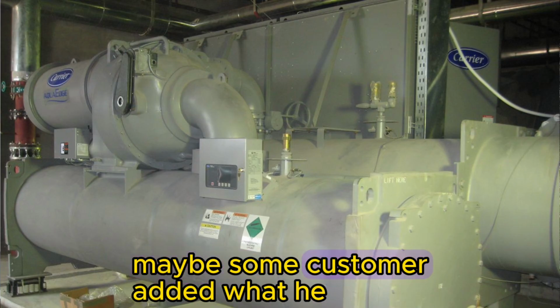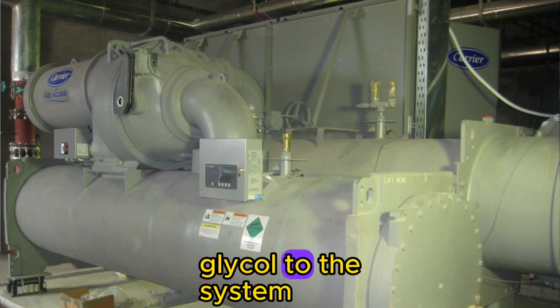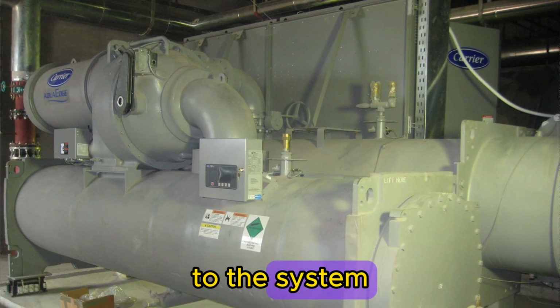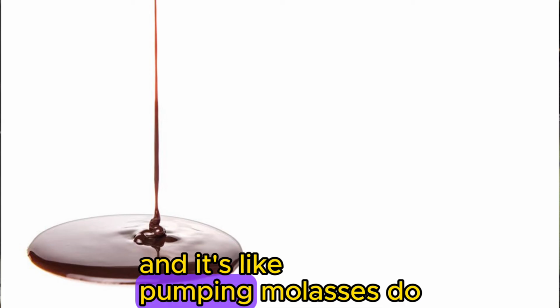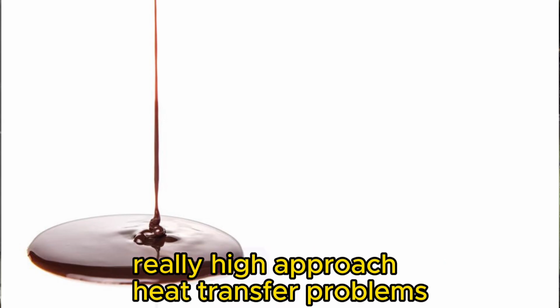Maybe the customer added what he thought was mixed glycol to the system, or he just added pure glycol, and it's like pumping molasses through there. You don't get flow, you have suction pressure problems, you have really high approach, heat transfer problems, etc.